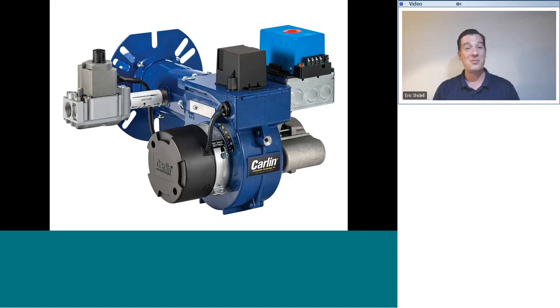Here is the fan motor, and in this housing is the fan, and it is blowing down the tube away from you in this direction. Notice gas is introduced into that discharge air stream so that the fuel and the air can mix in this portion of the burner tube. Flame happens at the very end of the burner, pointing horizontally. There is an opening that can be adjusted with this little adjuster band. The opening is actually around the back of this thing. You can't really see it, but you could stick your fingers in there. That's our primary combustion air opening.